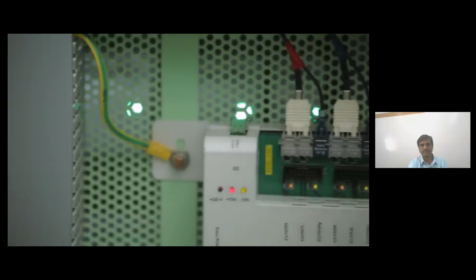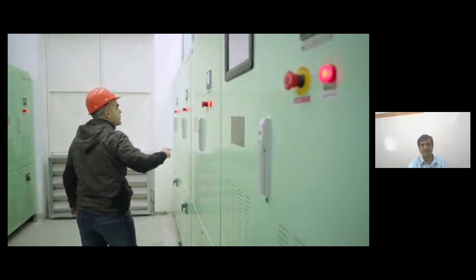ABB designed and supplied a power electronics-based compensation solution for dynamically varying reactive power called PQC StatCon, installed in various nodes across the rail network. In simple terms, PQC StatCon is an instantaneous and stepless compensator for improving power factor and reducing voltage variations. When connected to the load, it reduces demand on the electrical network by instantaneously compensating the reactive power.